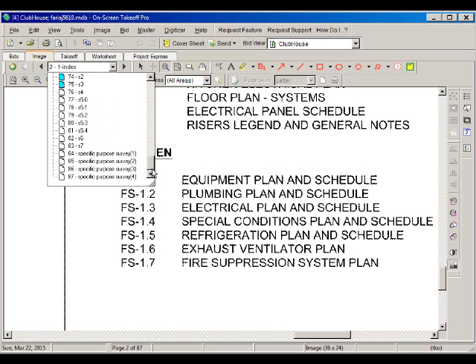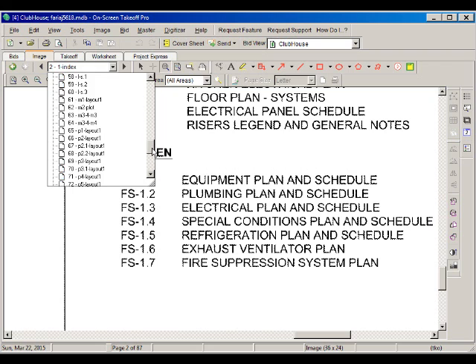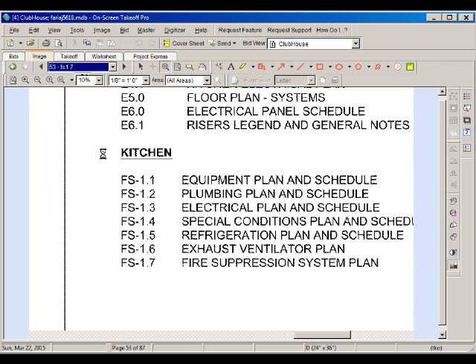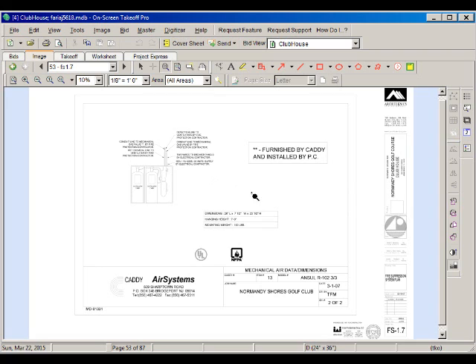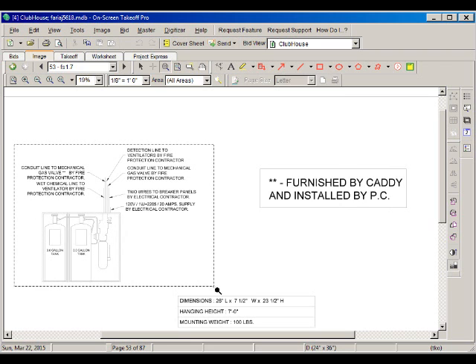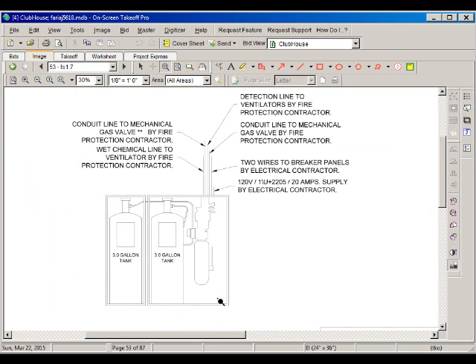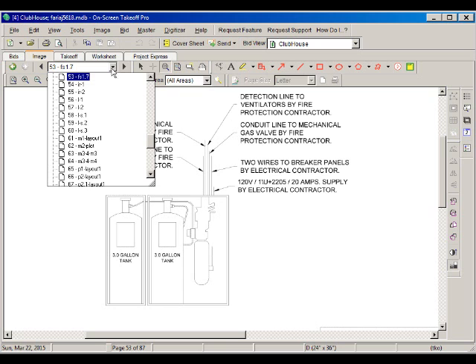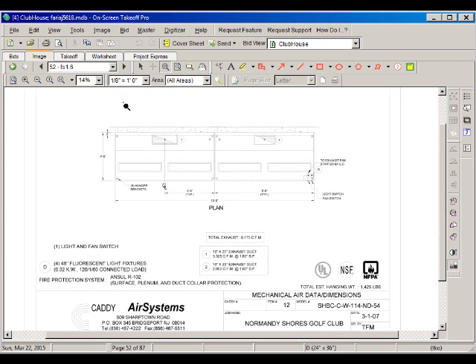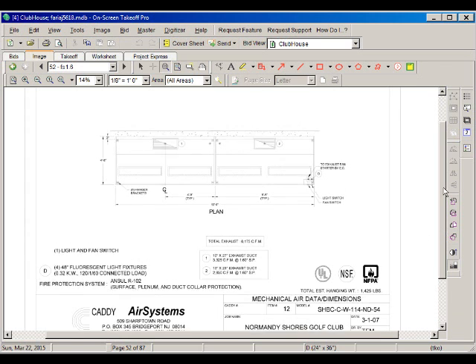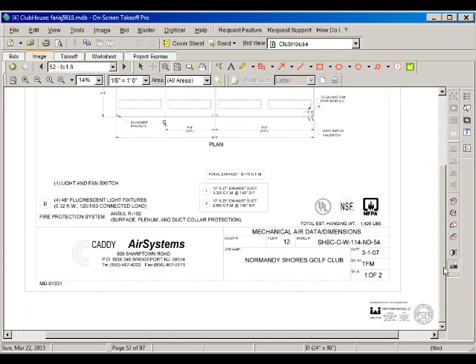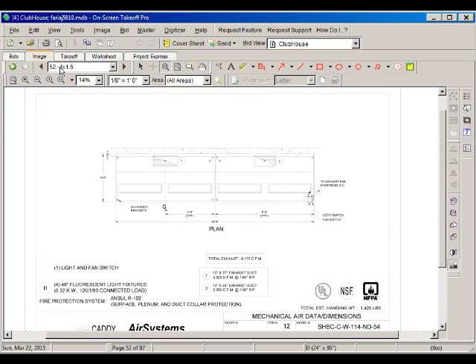Drawing FS-1.7, we see here that this is a system furnished by some manufacturer and it does have a fire protection system with two 3.0 gallon tanks. These tanks are going to provide some sort of fire protection to the kitchen.